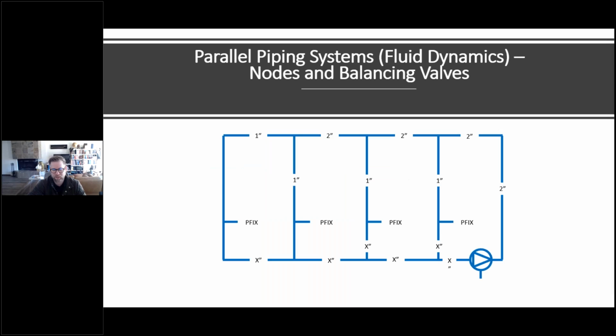And this is even fairly simple. When we're evaluating parallel piping systems, the first step we got to take is look at what the nodal points are. So in this case, I have here in the bottom, let me get my laser pointer out. In the bottom corner here, we have a pump symbol that's representing our recirculation pump, our water heater source, and then there's a little line off the bottom of it that represents our cold water makeup. But this is a hot water recirculation system.